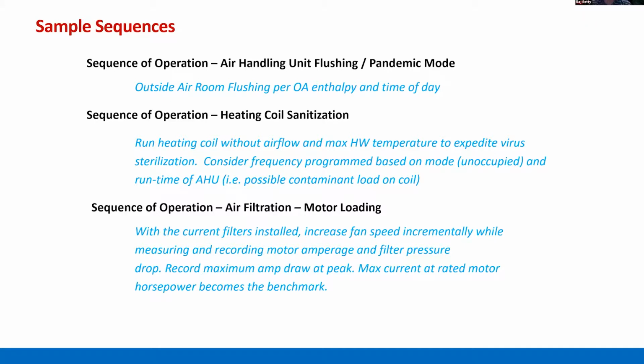So going through the three sequences that you see here, and then I'm gonna add a fourth one. On the air handling unit flushing, if your building operators are gonna open windows, make sure that that is also taken into consideration. And as soon as the windows do open, then the air handlers should go into economizer mode. So that way you're not going to overcool or overheat and waste energy. So that's one, so just think about that. I know New York City schools, that is the MO, open the windows.